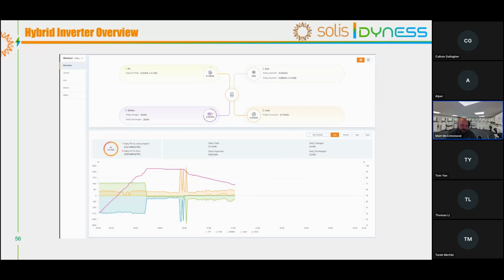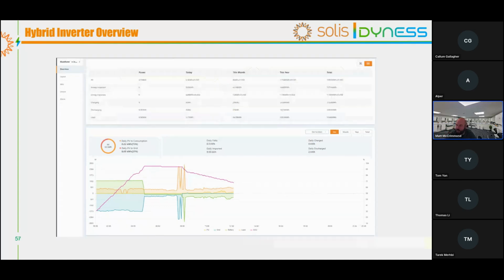It then plots a load profile throughout the day, and then you can see the SOC climbing. So on this, for example, you can see there's a time of use window because it's completely ignoring what the load's doing. It's just charging the battery between the hours of 12 and 5 there, by the looks of it, up to 100%, and then slowly discharges through the day to offset your energy costs. So you can see all this information. You can also flick back per day on that. So you can see per day, per month and per year, and then you can also select total. So there's a few things that the customer can do just basically as an overview. And that should be good enough for your end user.